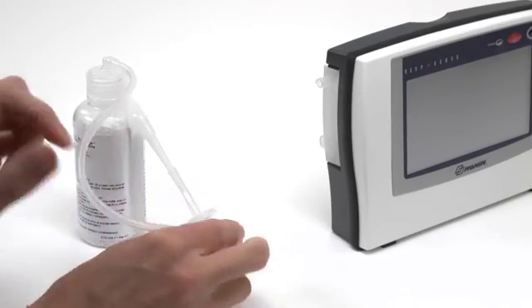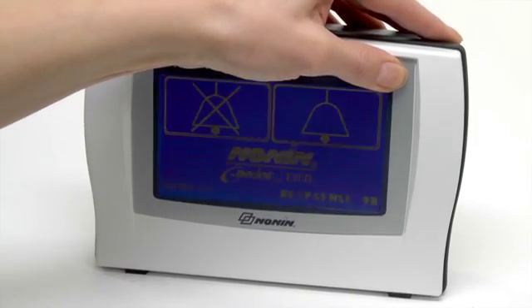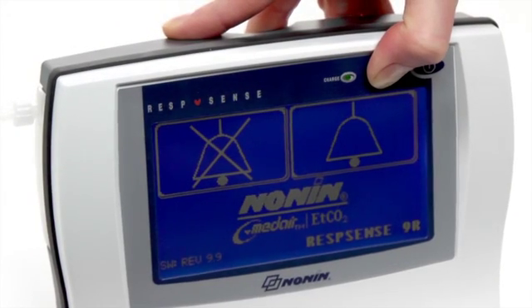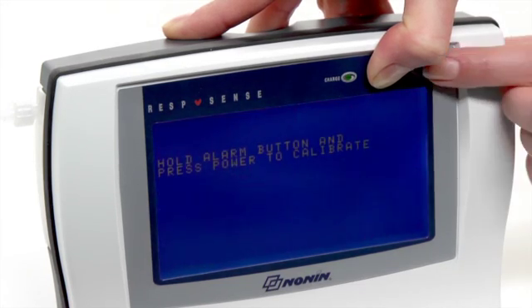First, attach the calibration apparatus to the moisture trap. Turn the monitor on. When the Nonin logo appears, press and hold the audible alarm pause/resume button. Keep that button pressed and press the power on/off button at the same time and hold.